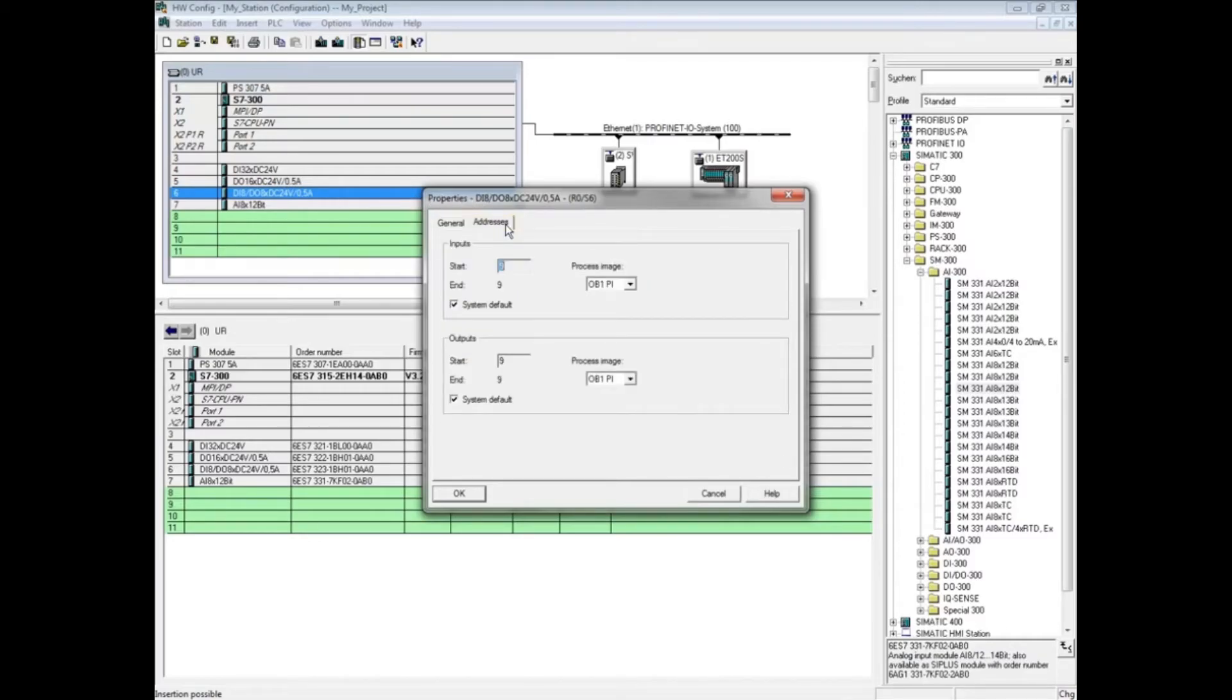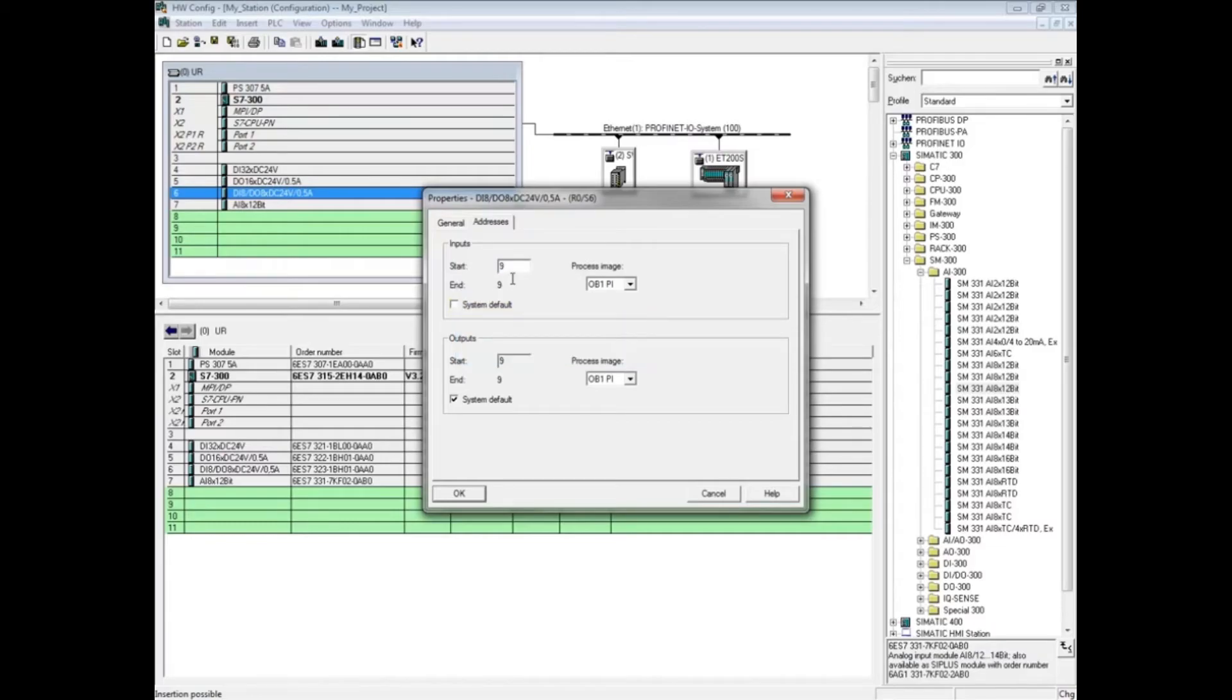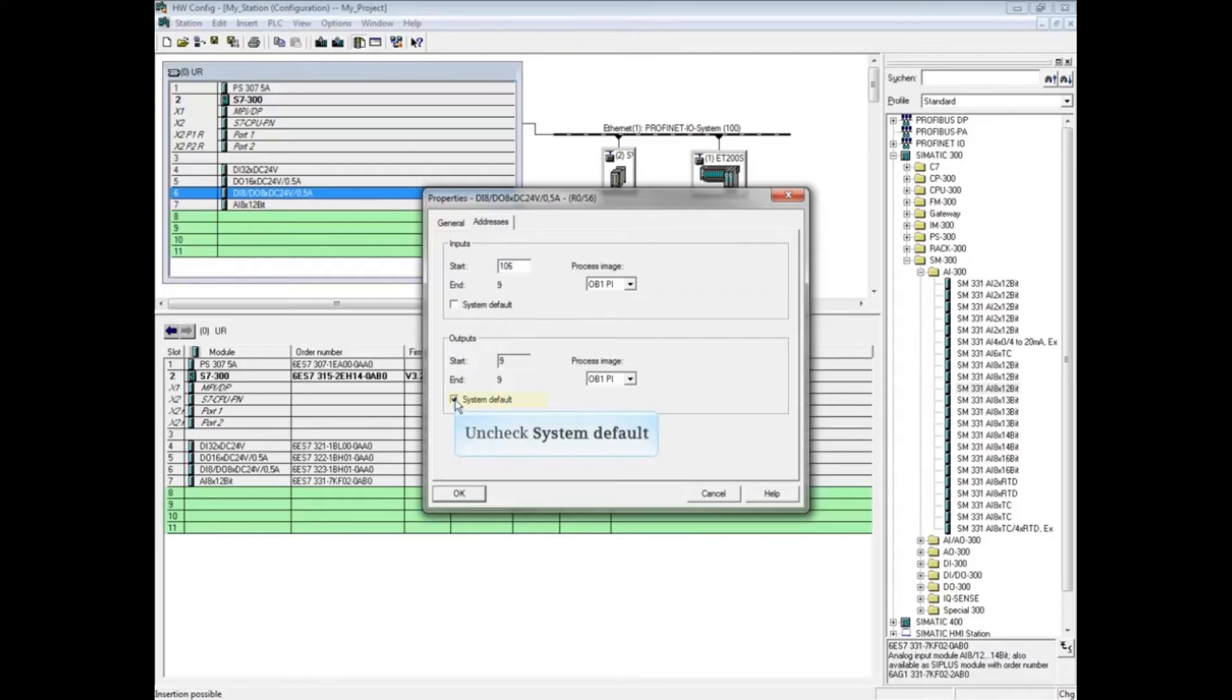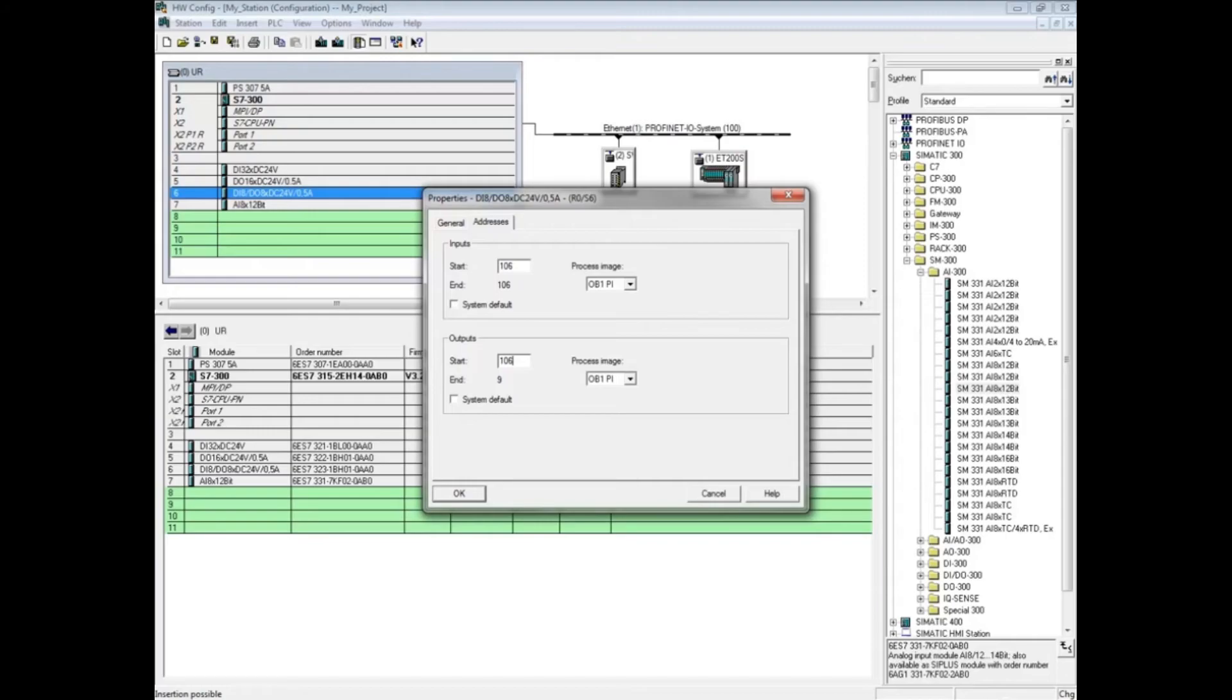Uncheck system default for the input address. We will change the input address to 106. Uncheck system default for the output card. We will change the output address to 106. So this card will occupy input byte 106 and output byte 106. Click OK.